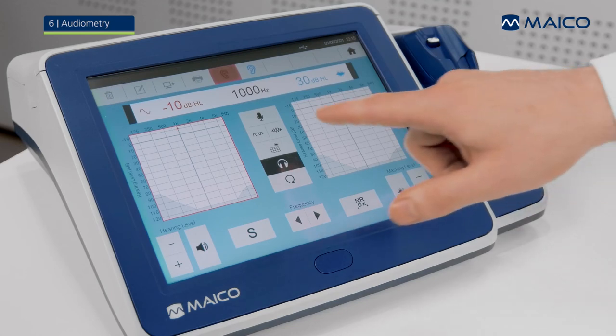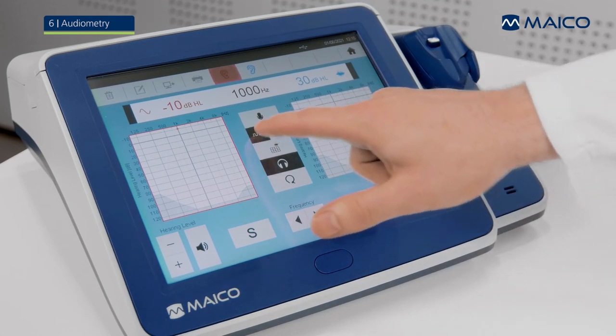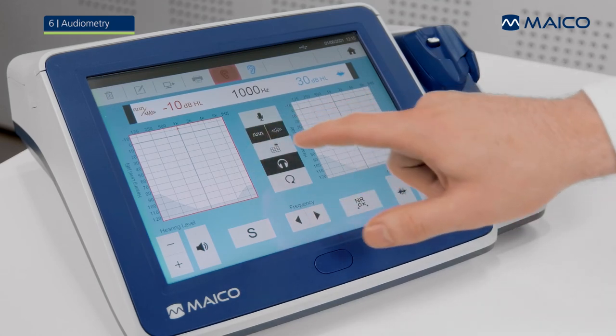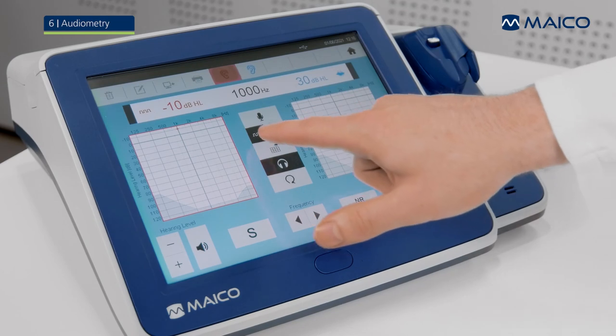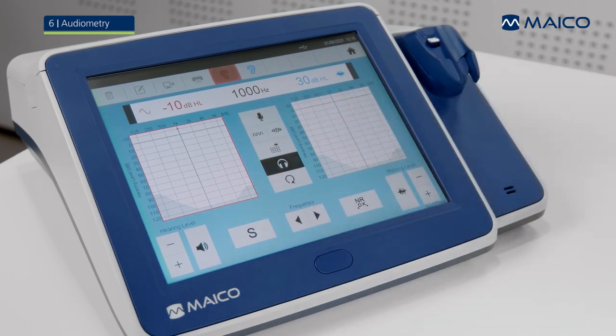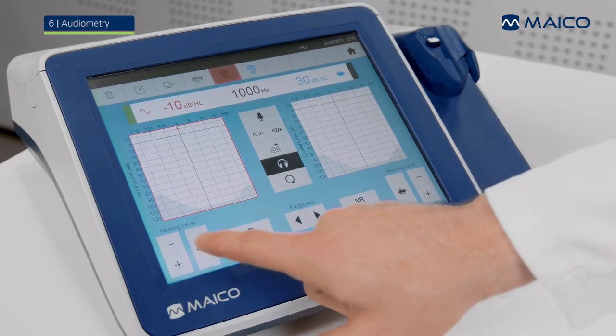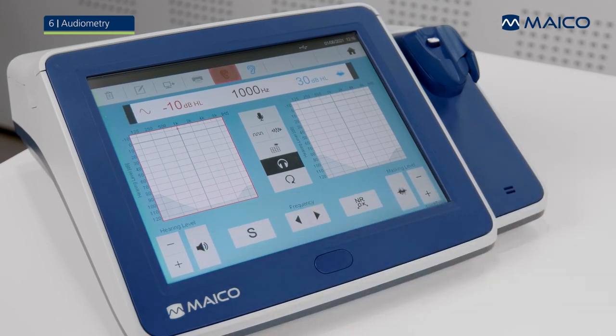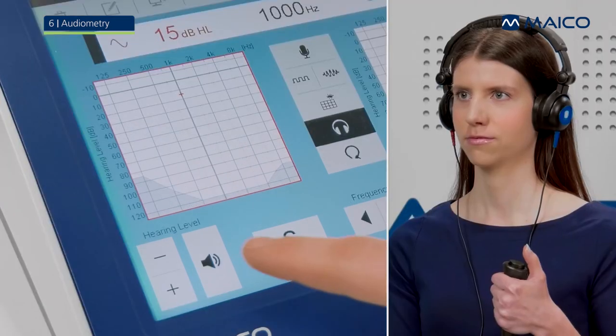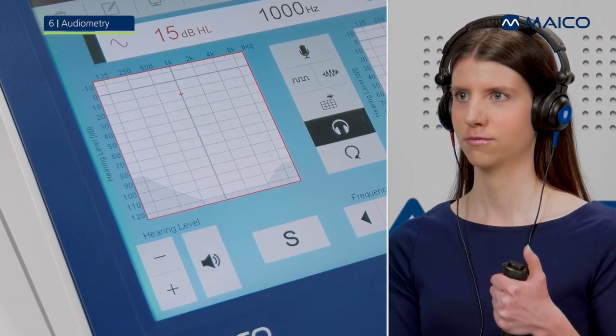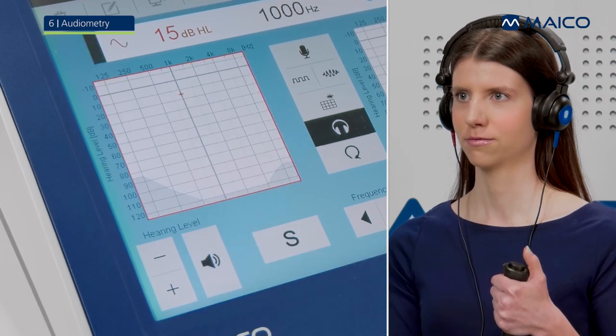The test stimulus button is used to choose between steady, pulsed, wobble, and pulsed wobble stimulus presentation. Pressing the presenter button presents the stimulus to the patient. Depending on the settings, it can be used in presenter or interrupter mode. The patient response is indicated within the audiogram.